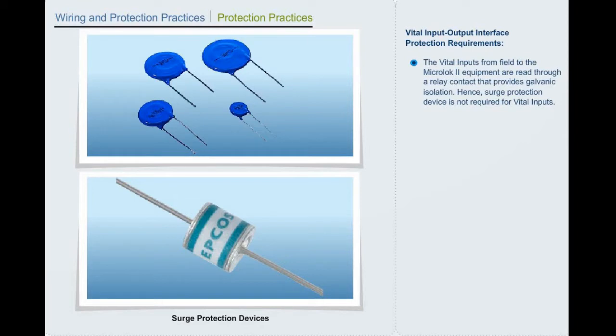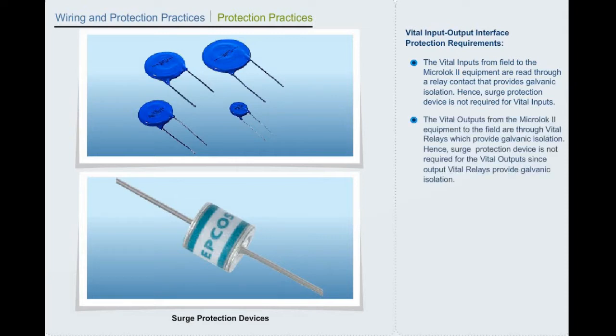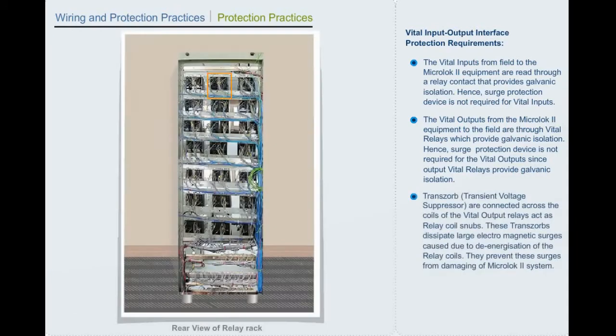The vital inputs from field to the Microlok II equipment are read through a relay contact that provides galvanic isolation. Hence, a surge protection device is not required for vital inputs. The vital outputs from the Microlok II equipment to the field are through vital relays which provide galvanic isolation. Hence, a surge protection device is not required for the vital outputs since output vital relays provide galvanic isolation.